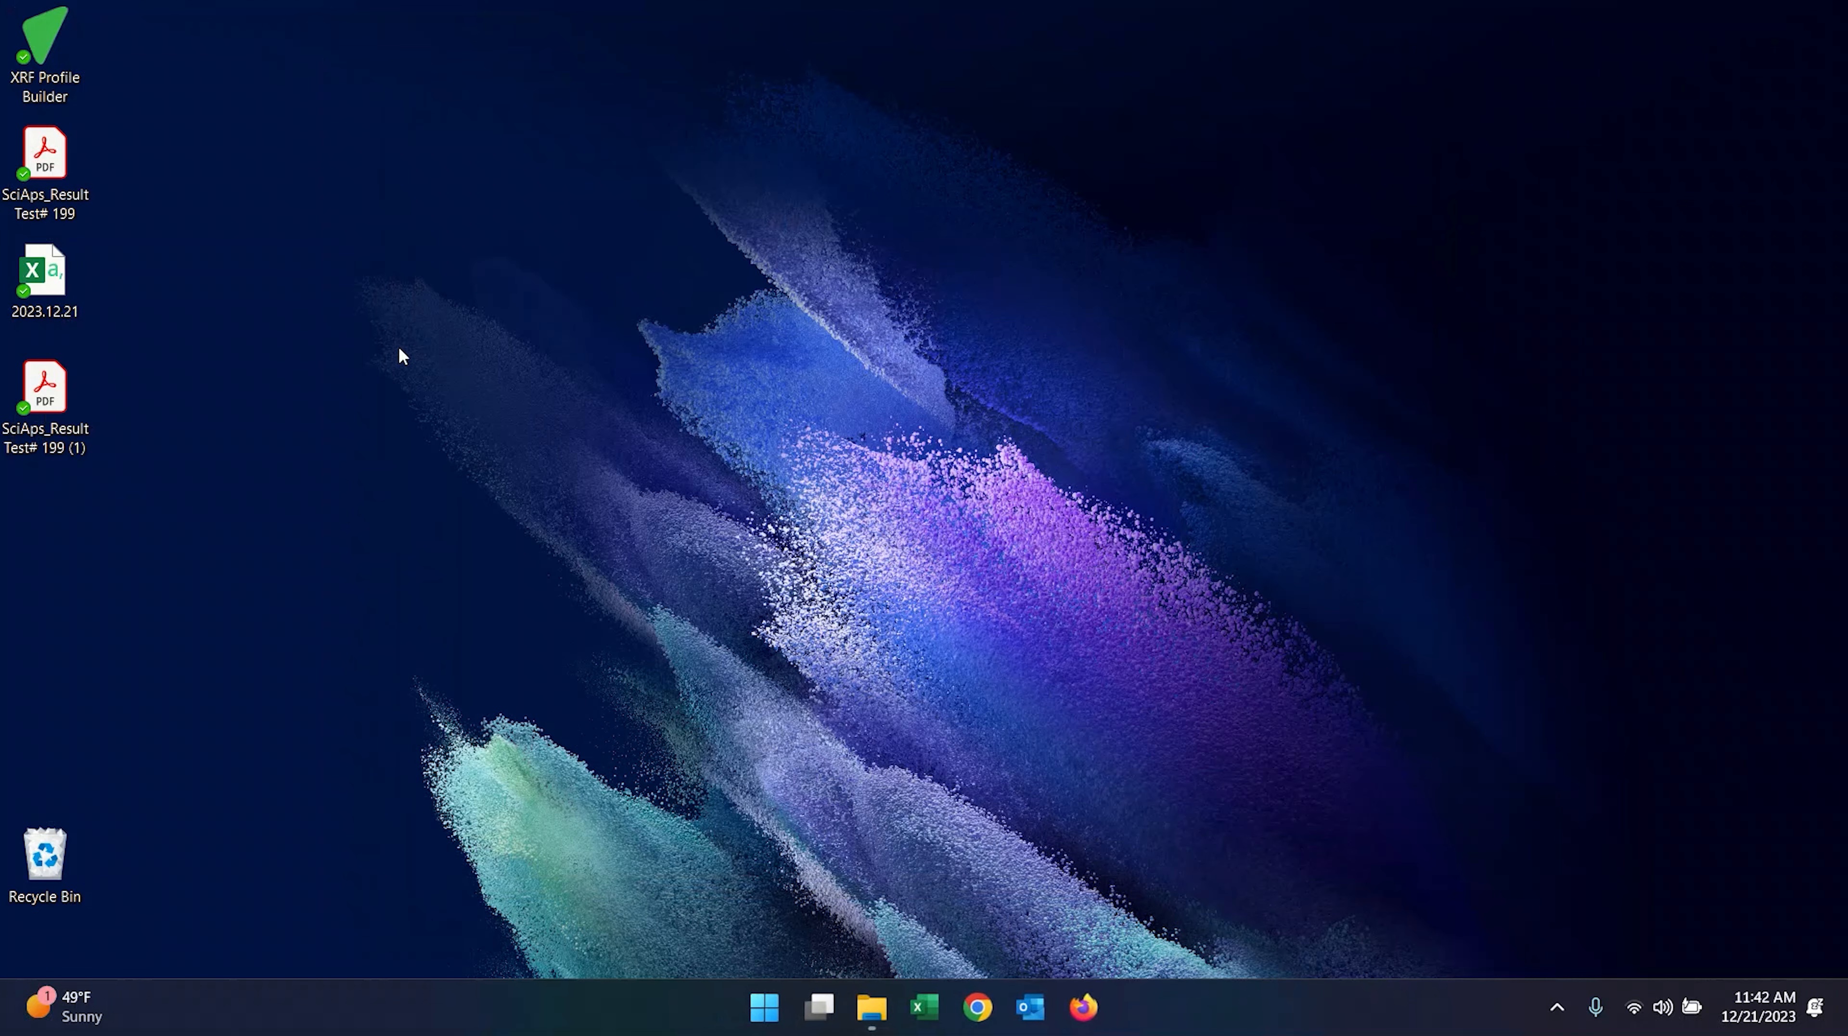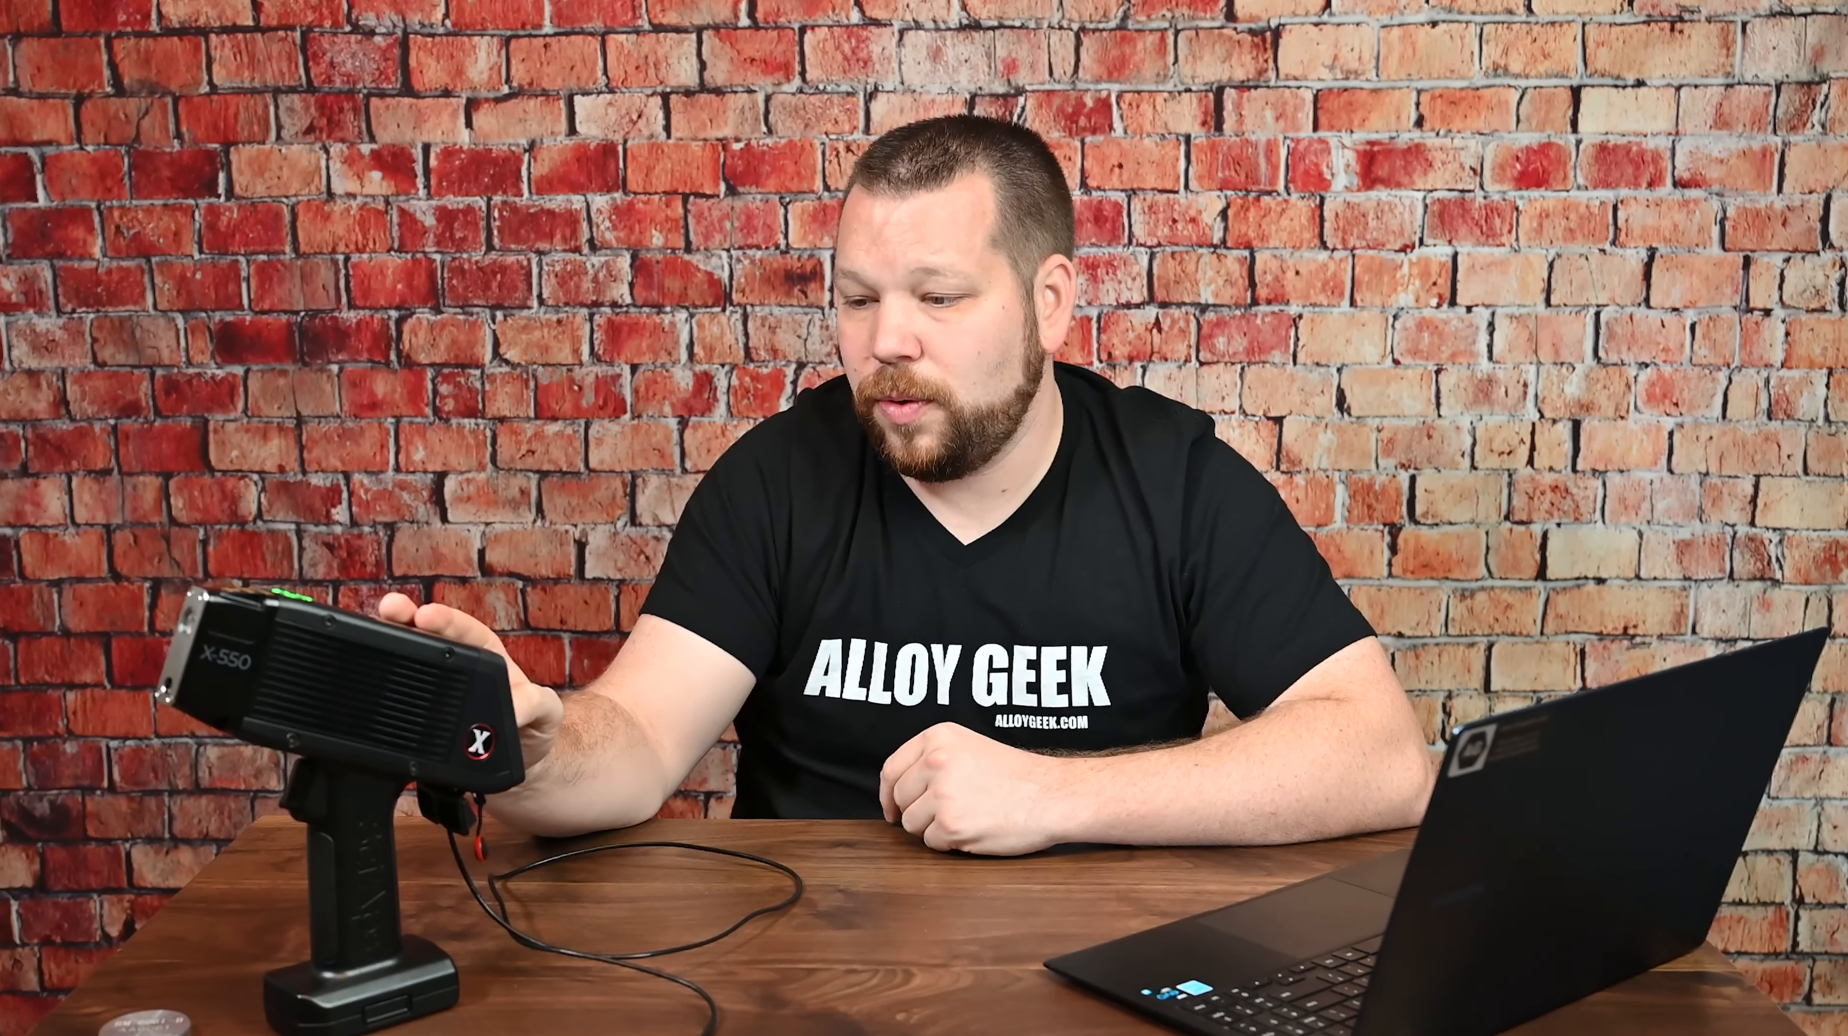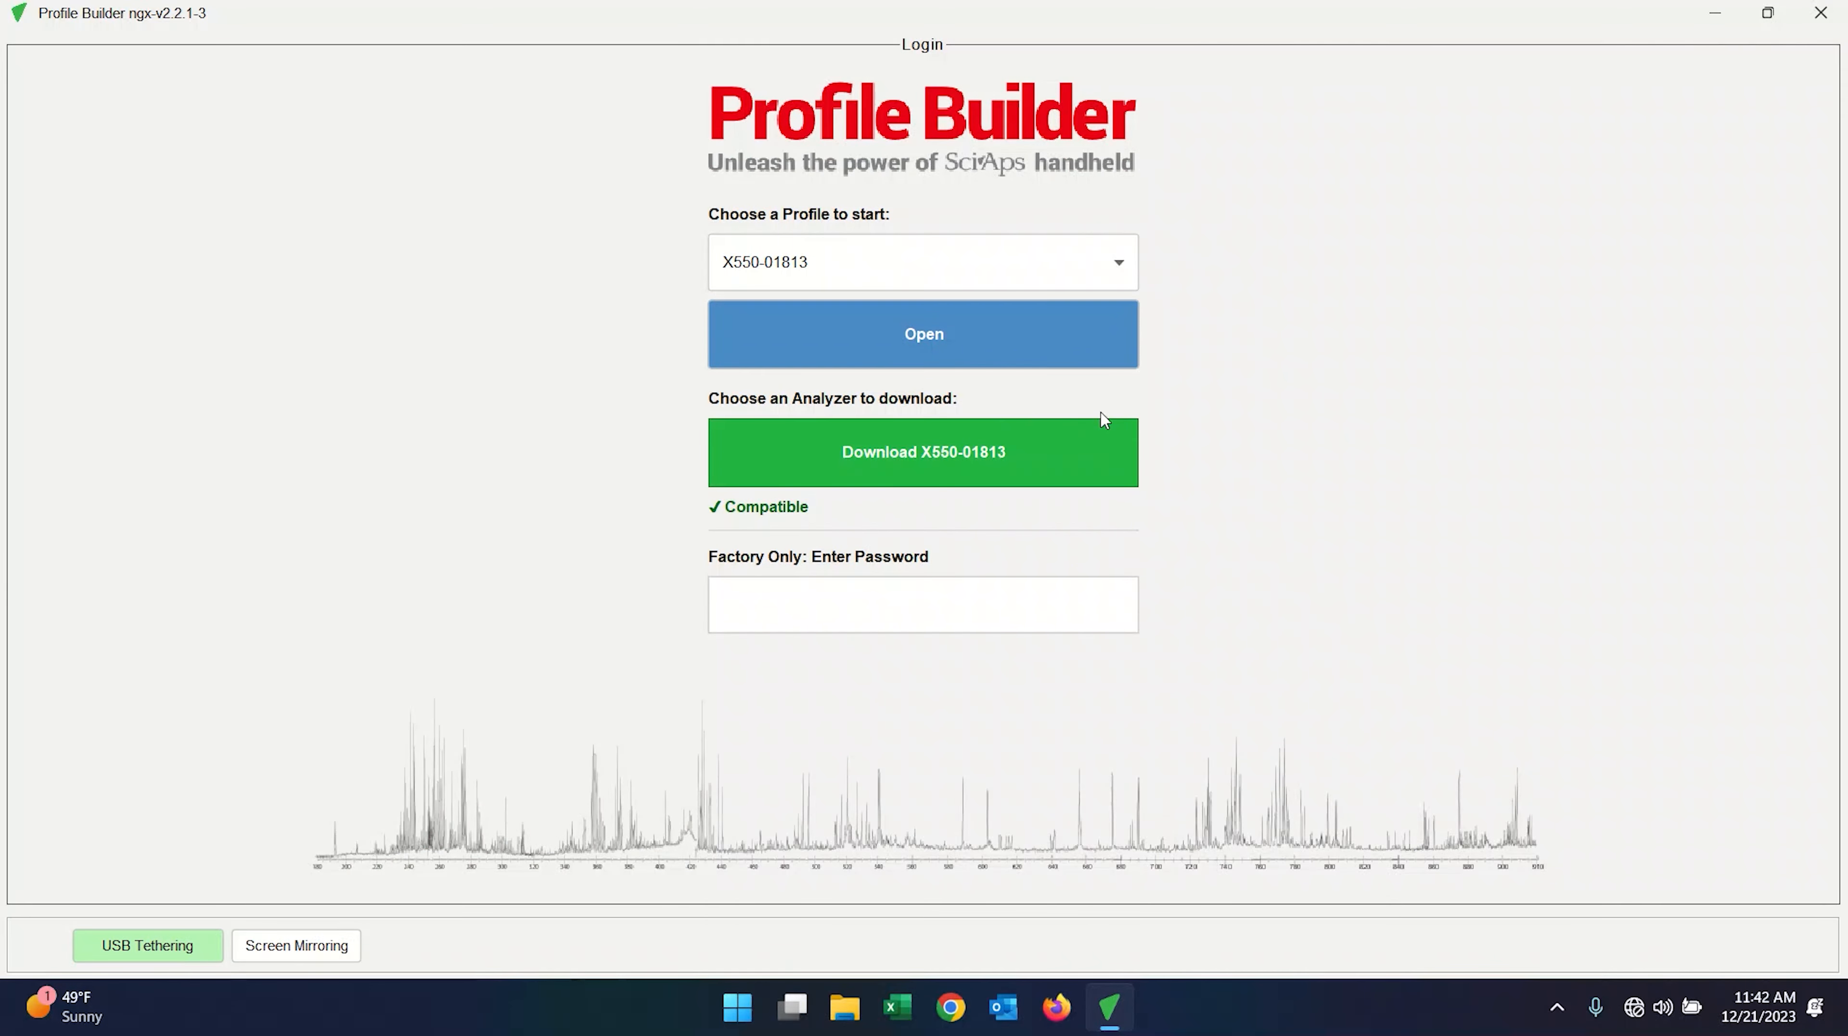In fact, I'm going to exit that so you guys can see how it loads, because I think that's important for how we connect to it. And I'll show you even how I mirrored my screen here. So you'll see this screen first, and you'll see USB tethering in the bottom left and it's red. So what we actually have to do in order to get USB tethering to work, to show you guys the screen and other things like that, you're going to swipe the analyze screen to the right, and you're going to select remote service. Now, once you do that, you'll notice that choose an analyzer to download this big green button here that pops up. That's what you want to see. If you don't see that, you might again have USB ports that are blocked, but you can click that.